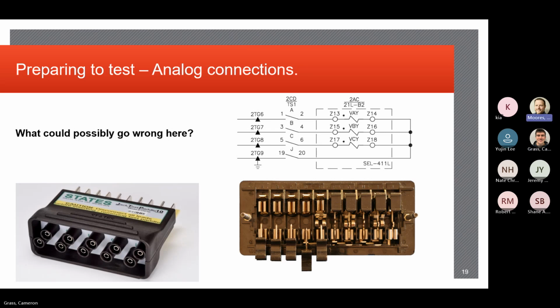I've seen this in service before like this, and you've got to be very careful because you think you have an isolated relay, but you're actually plugging into a live voltage, live DC, live whatever. Or to Cam's point, if it's de-energized and you accidentally turn a test set on and put some currents and voltages in there, maybe somebody else is working on that circuit downstream. They think it's isolated and it's not. So anybody have questions on what this is illustrating?